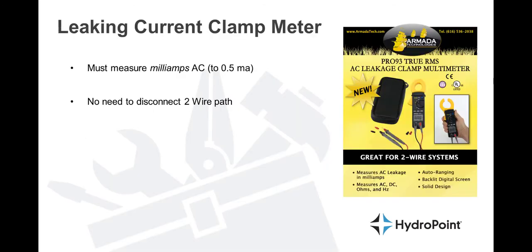To run this test you will need a special type of voltmeter called a leaking current clamp meter. The one we use is from Armada — we recommend the Pro 93 as the standard. Any leaking current clamp meter will do as long as it measures milliamps. What this tool does is allow us to measure the current in the system without disconnecting the individual splices, which saves an immense amount of time and money.